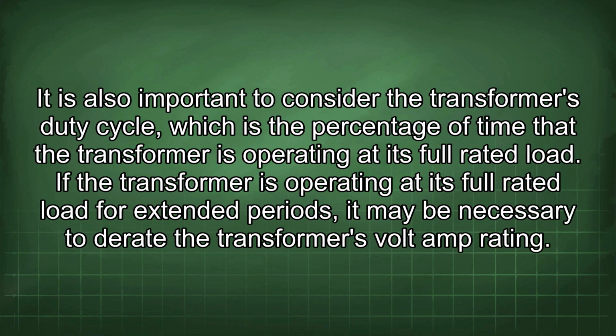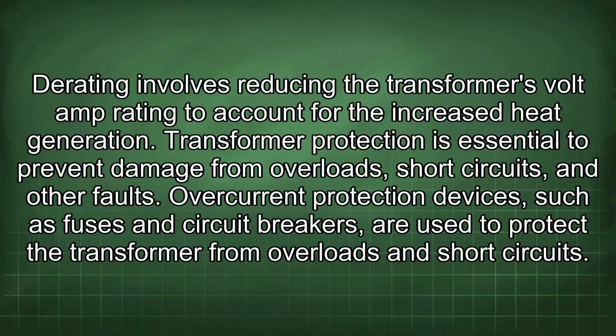It is also important to consider the transformer's duty cycle, which is the percentage of time that the transformer is operating at its full rated load. If the transformer is operating at its full rated load for extended periods, it may be necessary to derate the transformer's volt amp rating. Derating involves reducing the transformer's volt amp rating to account for the increased heat generation.